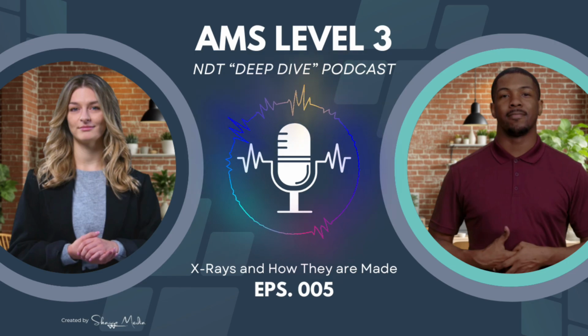Okay, let's talk about that power. The high voltage sources, we need huge voltages. We do. We're taking standard mains voltage, 100, 240, maybe 460 volts, and stepping it up massively, anywhere from 5 kilovolts, so 5,000 volts, up to 420 kilovolts or even higher for some industrial units. How did they do that initially? The simplest circuits were self-rectified. Basically, the X-ray tube itself acted like a diode, only allowing current to flow when the anode was positive relative to the cathode during the AC cycle.